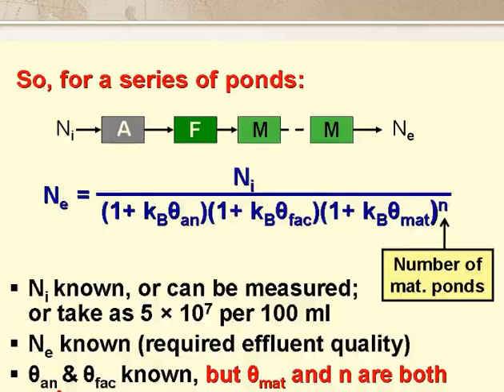NI is either known or taken as, for example, 5 times 10 to the 7 per 100 ml. NE is known, as it's the final effluent quality we need. At this stage in the design, we will have already designed the anaerobic and facultative ponds, so the retention times in these — theta-an and theta-fac — are also known.